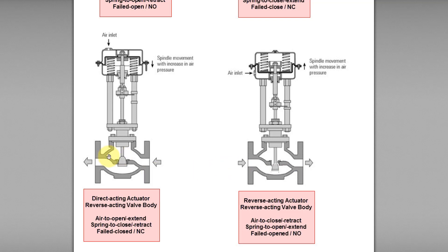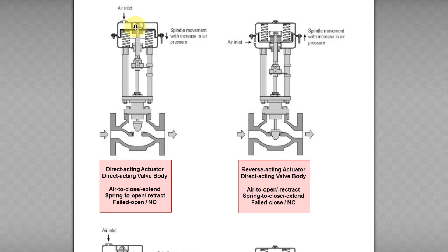This control valve is called an air-to-close control valve. Sometimes people use other terms such as air to extend, spring to open, spring to retract, or fail-open control valve. It is called air to close or air to extend because when air is applied to the top portion of the actuator, the instrument air pushes the diaphragm and spring downward. As a result, the stem — sometimes called spindle or shaft — extends downward to close the valve body.